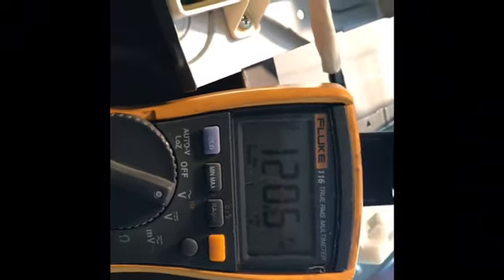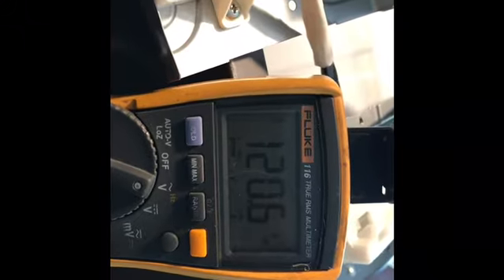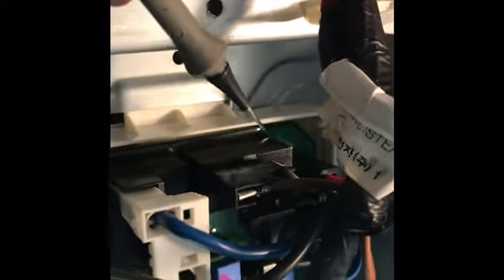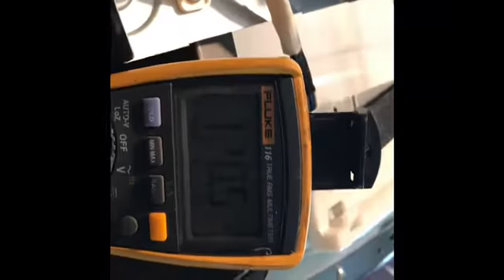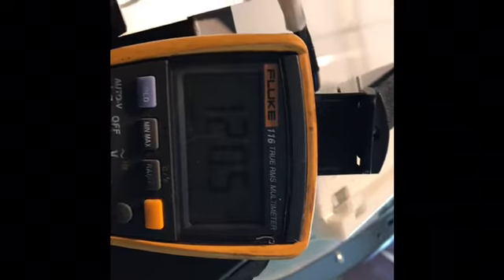So we got 120 right there. That's a quick and easy way to check that we got voltage coming to the main, going through the motor centrifugal switch to coming out this motor relay. You got the 120 there. And this other one's for your heater once it starts up. You might have some standby voltage there. We have 120 volts on the heater relay as well, so we're switching line 1 once it powers up.